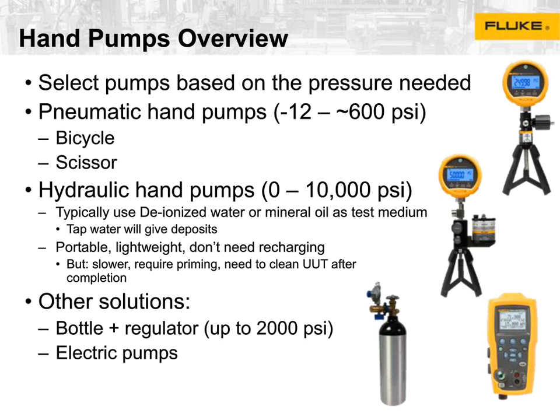And the most important thing to remember about hydraulic pumps is that the fluid that you use in those pumps makes a huge difference. Pretty much all manufacturers will recommend that you use deionized water or mineral oil. If you use tap water, you are going to be unhappy, because the tap water will give you deposits, and eventually your pump won't prime and you won't be able to use the pump until you clean it. And cleaning it is absolutely no fun. You only have to do it once or twice, and you'll remember to never use tap water again.